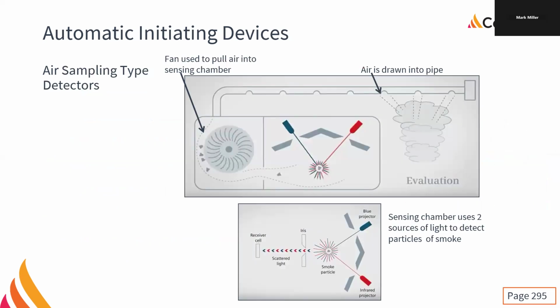So it works just like any other smoke detector. Right? They are only available as a photoelectric. That's all they designed it for. But we're using a fan to actively pull the smoke in, and then we use our light projectors and receivers. But we're also using two different wavelengths at this point. We use a blue light and an infrared. So we're working at both ends of the visible spectrum. Like yes, infrared is technically outside the visible spectrum, but only just, right? So we're looking at two different wavelengths because we're trying to be very, very specific, and we're looking at some pretty extreme sensitivities here.